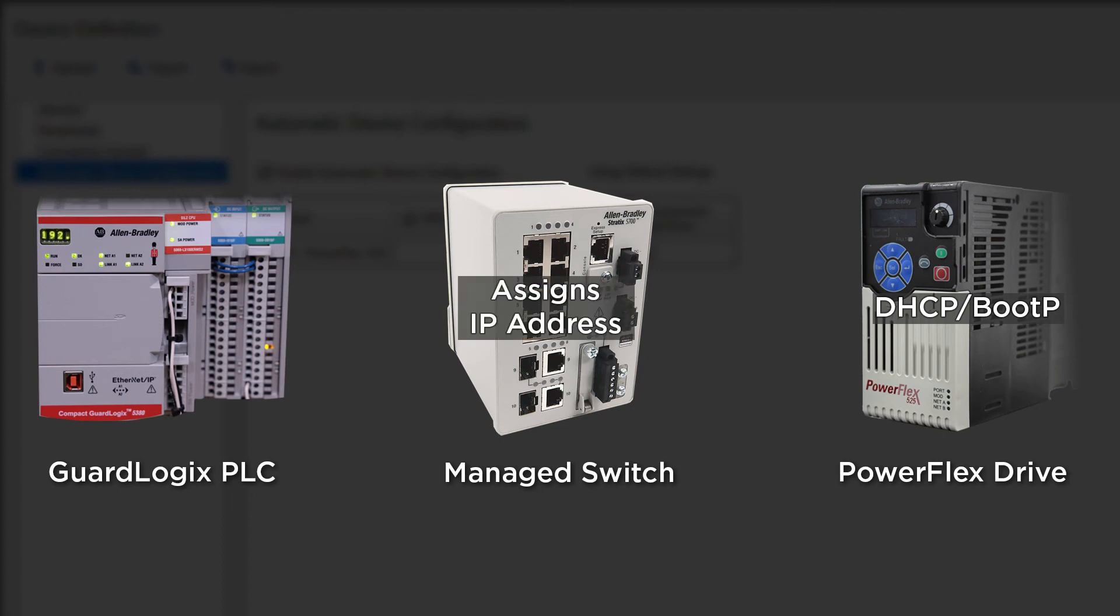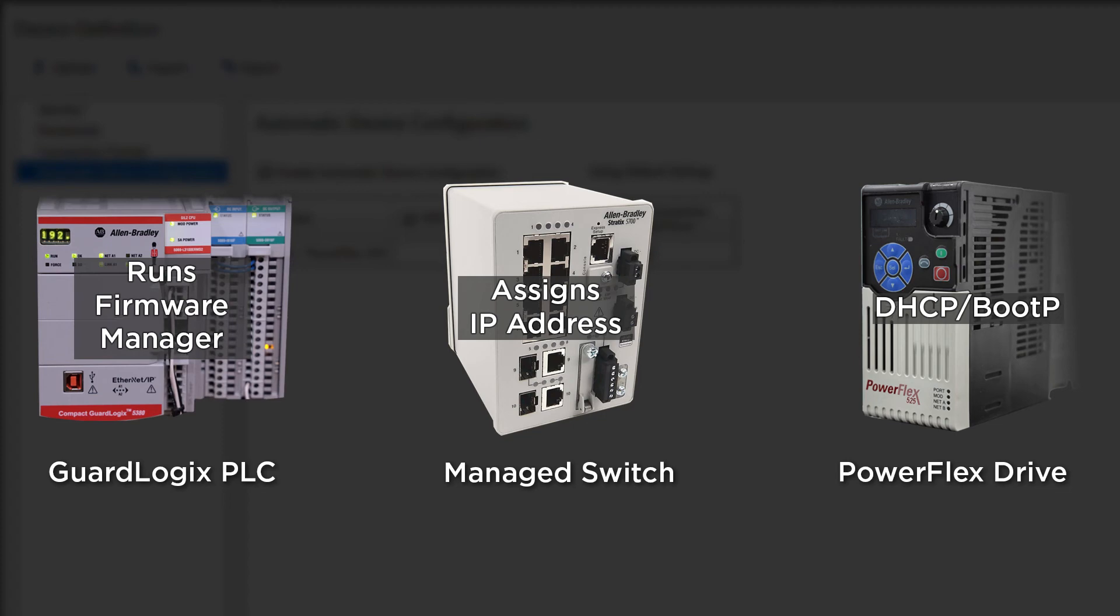Once the address is seen by the controller, it will run the firmware manager. If the firmware is different, it will download the proper firmware. If it is the same, then it will start checking the parameters of the drive. If any differences are found, it will automatically update them and the whole system will go back into operation.